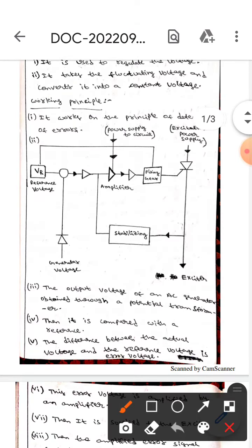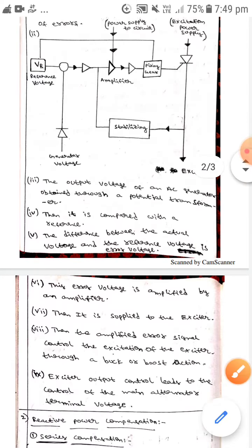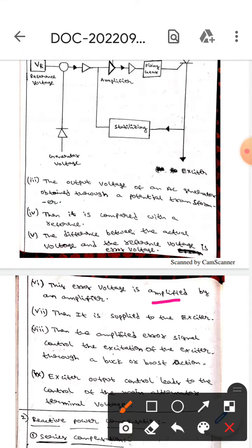The output voltage of an AC generator is obtained through a potential transformer, then it is compared to a reference. The difference between the actual voltage and reference voltage is the error voltage. This error voltage is amplified using an amplifier.